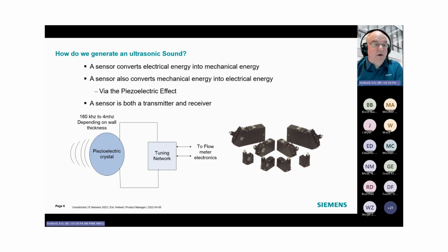Well, to be short and sweet about it, if you're putting them up on an Alaska pipeline, we have meters that have actively been working for many years, they're mounted and installed with a little bit of insulation. The pipes are usually warm, and that doesn't usually promote any problems, especially if the pipes are flowing. If it's extremely hot, we have these working at 120, 130 degrees Fahrenheit out in the deserts in Dubai. None of that has been a problem either. So it doesn't affect the installation whatsoever because it's a physical installation. It's strapped to the pipe. But you have to be aware that if you're going to cause frost or anything like that, you want to make sure that that's protected. It usually isn't a problem. It's just like if you're putting it underwater, you actually have to waterproof it.